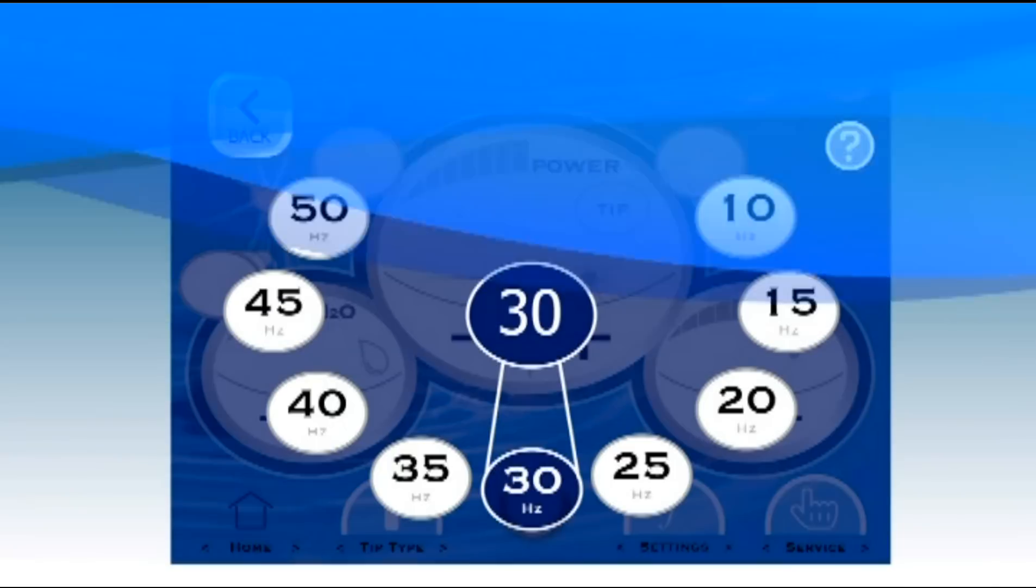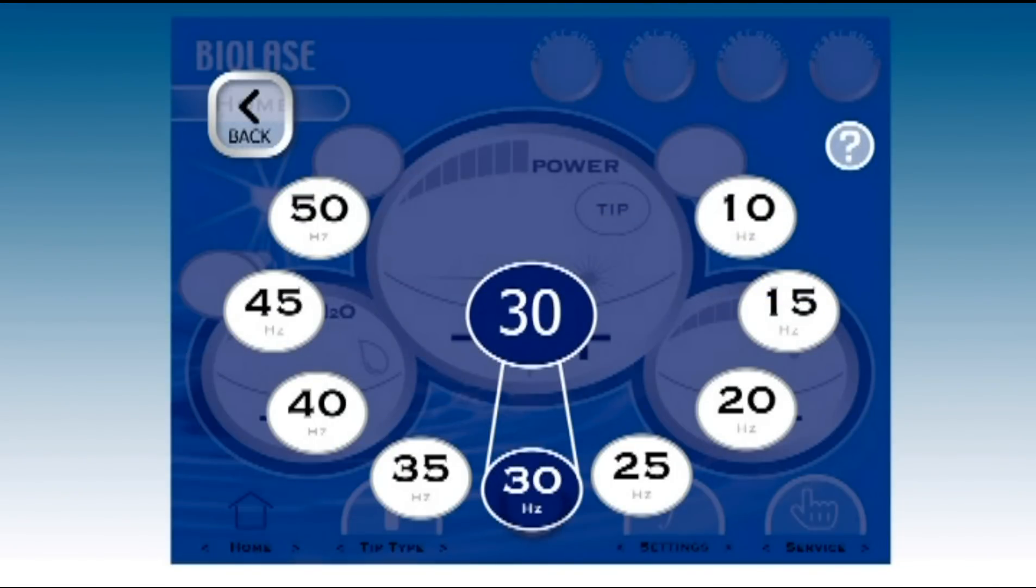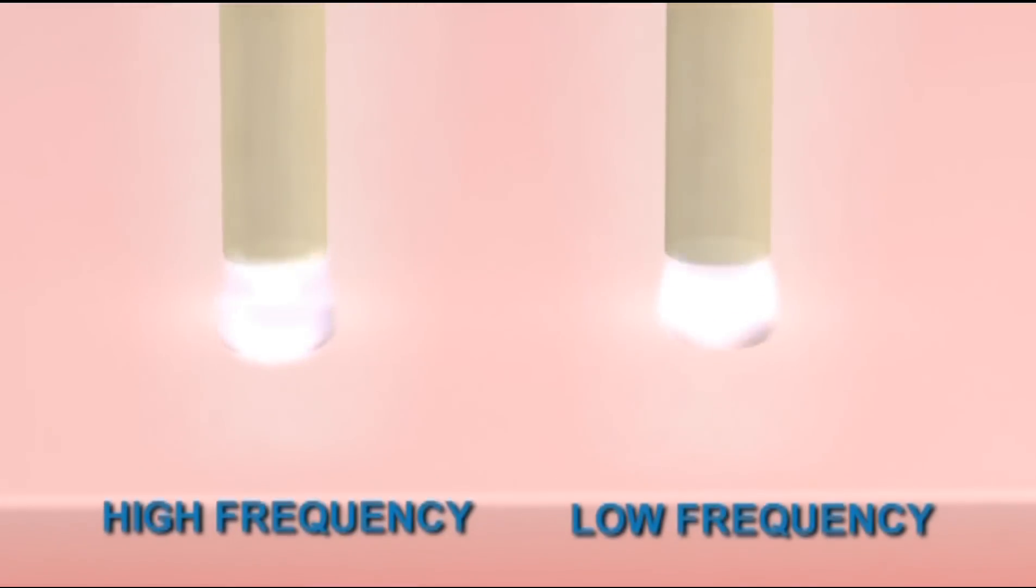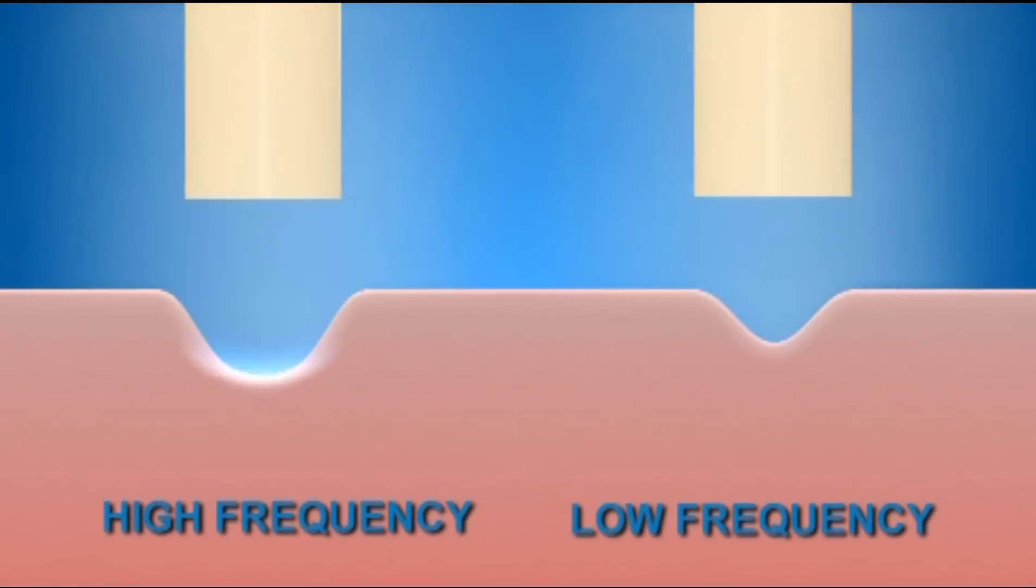Frequency, or the number of laser pulses per second, controls the smoothness and speed of cutting. Higher frequency produces a smoother cut, since there are more cutting pulses for any given length of incision. High frequency also cuts faster. As with power, simply adjust the frequency for the results you want.